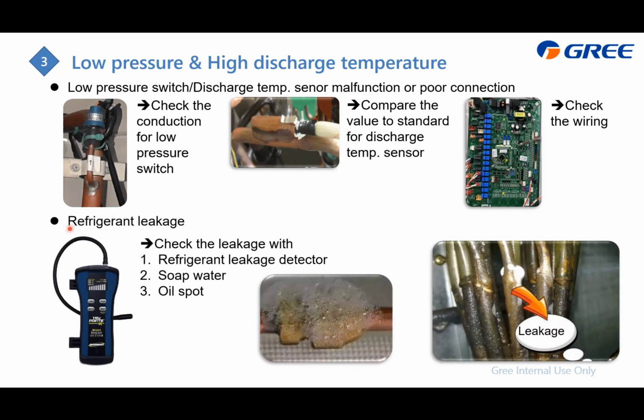And as for the refrigerant leakage, you can use a refrigerant leakage detector, or soap water, or you can check whether there's some oil spot on the refrigerant copper pipe. If there's some oil spot, that means there must be leakage. As you know, the oil and the refrigerant mix together. If there's some leakage, the refrigerant will come out, and of course it will bring the oil out, and the refrigerant will become gas, but the oil will stay.